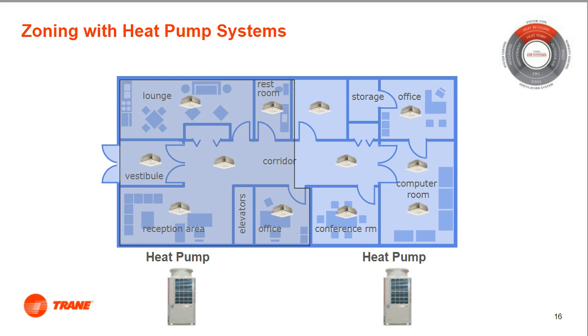For those wishing to use heat pump systems, even given their comfort risk, careful system zoning design is critical to minimize comfort complaints. It probably makes more sense to break up a building into multiple systems to increase building control flexibility. In this example, we show a small building zoning the west exposure separate from the east exposure. An hour-by-hour load analysis will help the system designer to determine if this will work effectively. Of course, if selecting a heat pump system requires the designer to select multiple systems, the cost savings of the heat pump option may be negatively impacted.